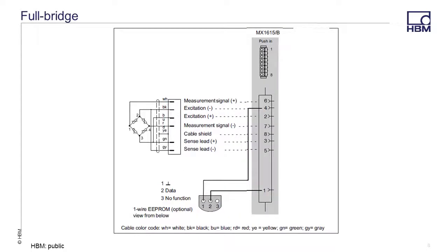Here is the full-bridge wiring connection for an MX1615B. Note that the MX1615B supports six wire bridge connection. Therefore, if you have a full bridge with only four wires in the cable, you must jumper the sense leads to the excitation leads at the connection to the amplifier.